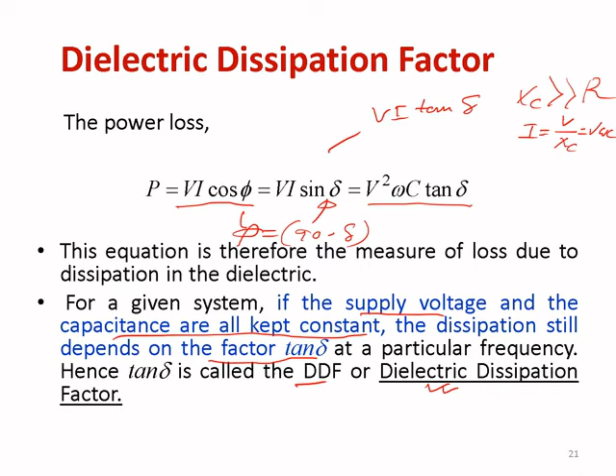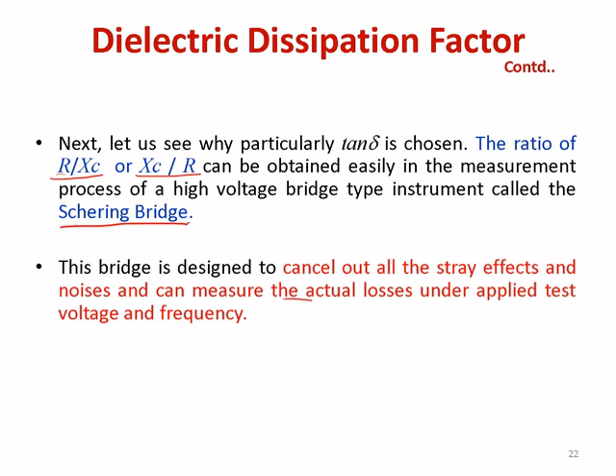Now frequently you have to measure the tan delta to judge the quality of the insulating materials, and generally we measure the tan delta in terms of circuit parameters R and C. So for the measurement, either we have to know R by Xc or we have to measure Xc by R, in case of series and parallel equivalence. For measurement purposes, we use a special instrument called the Schering bridge, which is designed to cancel out all the stray effects and noises and can measure the actual losses under applied test voltage and frequency.